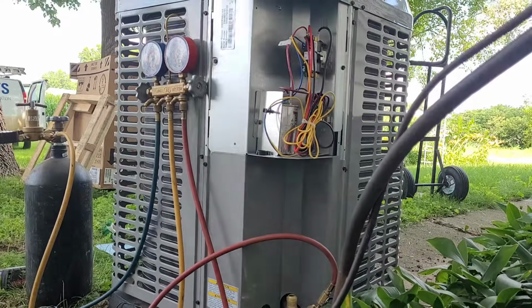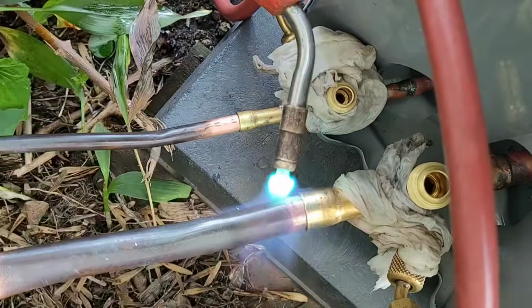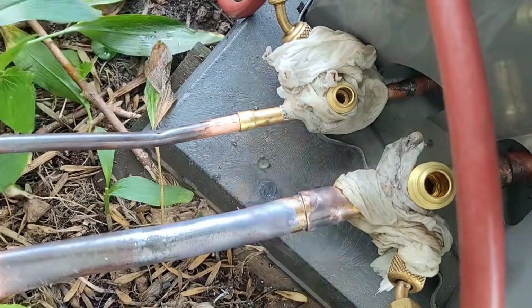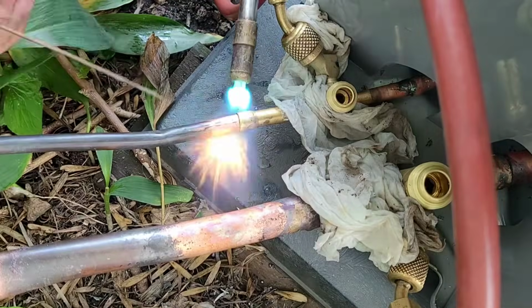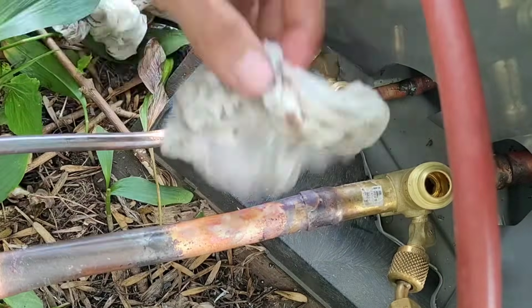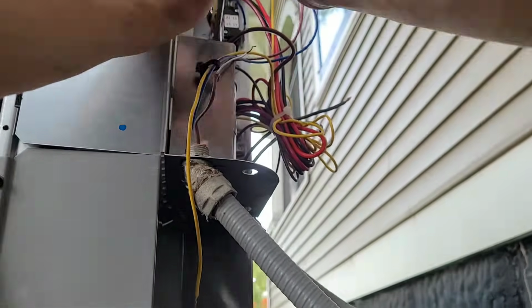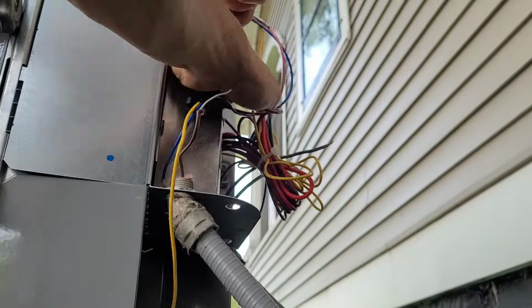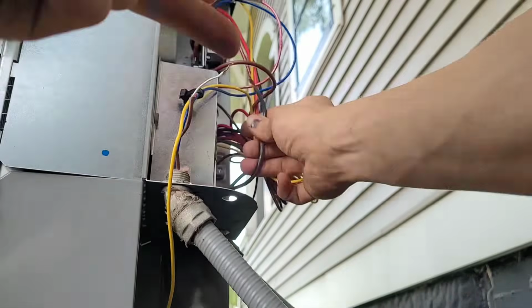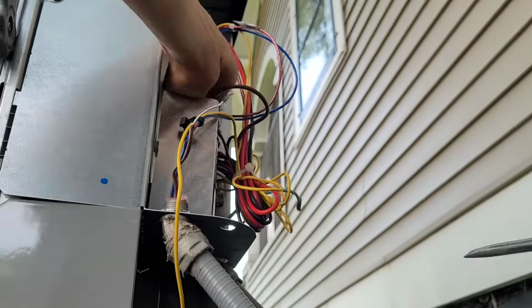Sort of like your roof isn't very tall compared to a skyscraper, but it's pretty tall if you fall off of it. Notice here that my refrigeration hoses are hooked up, and that's because I am purging some nitrogen through the line as I make these braze connections. Just got to be careful to not overheat the valves. And here I'm hooking up the wires. I really like that this system has a piece of conduit for both the low voltage and the high voltage wires coming to the unit.